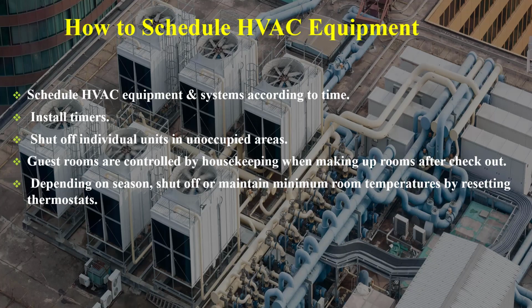How to schedule HVAC equipment. Schedule HVAC equipment and systems according to time if a building management system is available, or install timers and set on or off time intervals. Shut off individual units in unoccupied areas. Guest rooms are controlled by the guest room management system or by housekeeping when making up rooms after checkout. Depending on season, shut off or maintain minimum room temperatures by resetting thermostats.